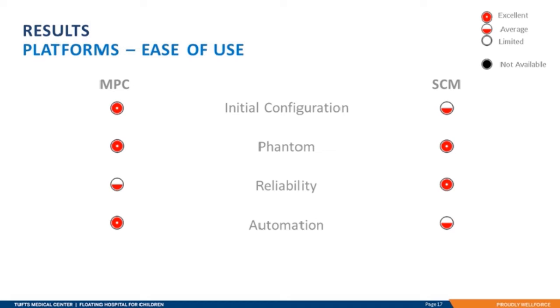The phantoms for both platforms are very easy to set up and use. We did find that we had more need on the MPC side to repeat tests due to results not capturing. SunCHECK Machine auto-saves, so the only issue we've experienced on that front has been user error.